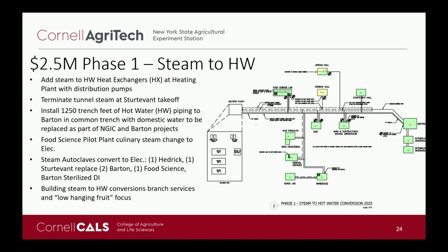So here again is the schematic. The first thought was that we could take the step toward district hot water by taking steam and making hot water in our heating plant, building out some backbone components for distribution. So the first phase is to do just that: set ourselves up with a hot water distribution system. In parallel with the NGIC building and the linear work we plan across campus to connect that domestic water project, we'll put in some EN 253 pipe and get the backbone of that hot water distribution installed.